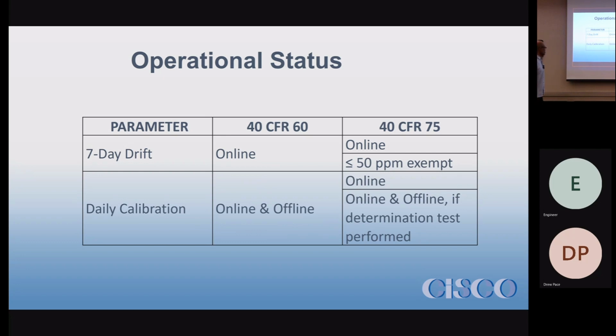For daily calibrations, online and offline calibrations can be used for both. The difference is under 60, you can use an offline calibration without doing anything extra. Under 75, you do what's called an online-offline determination test.